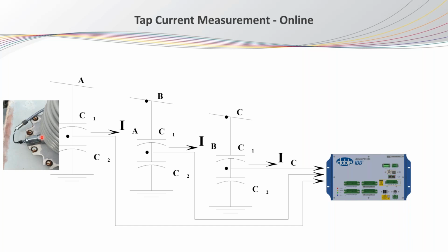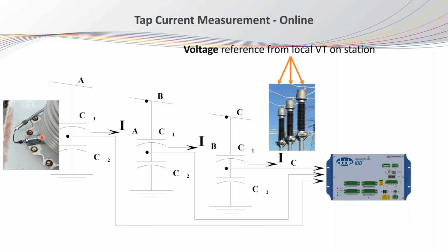In the online condition monitoring, we cannot apply voltage. So we can measure the voltage that is coming from the voltage transformers of the transformer circuit. And so we have the voltage from here. We measure the current through a sensor that we put permanently on the test tap of the bushing. And we can measure the phase angle between the measured voltage here and the measured current here. And we can also measure the capacitance from the measured leakage current. So we have the online power factor, we have the online capacitance 24 hours a day. Any deviation, of course, from the normal operation, we will need to move to the offline testing.